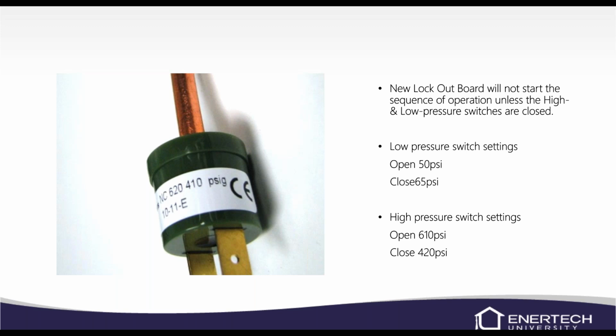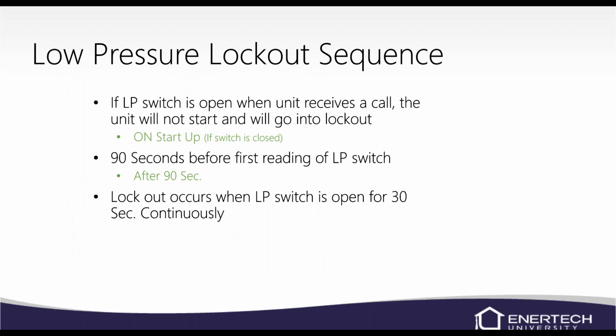Because the anti-short cycle is not there, it'll just see that switch is open, and it'll go into a hard lockout. So the low pressure switch is a setting of, it will open at 50 and it'll reset itself at 65 psi. The high pressure switch will open at 610 and it will reset itself at 420 psi. As long as the low pressure switch is closed when the Y1 call is received, it will wait 90 seconds before it reads it again. So it basically allows the compressor and your pumps to kind of get up to speed before it monitors the low pressure switch again.